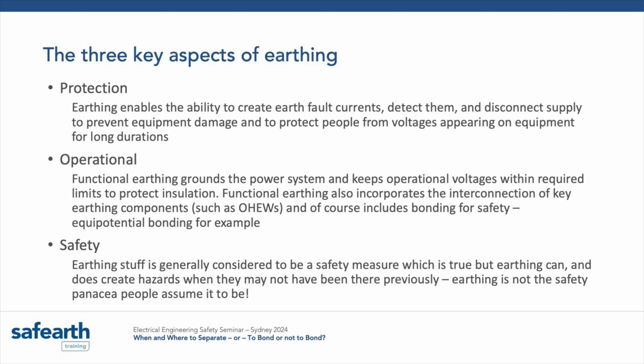Back to those three key aspects of earthing. I really liked when Tim Wiley talked about making sure you can initiate an earth fault. That's why we earth things, why we earth our equipment, why we earth the transformer at the start point, because you want to see that earth fault, detect it, and trip it as quickly as possible. So to me, that's the number one priority for earthing.